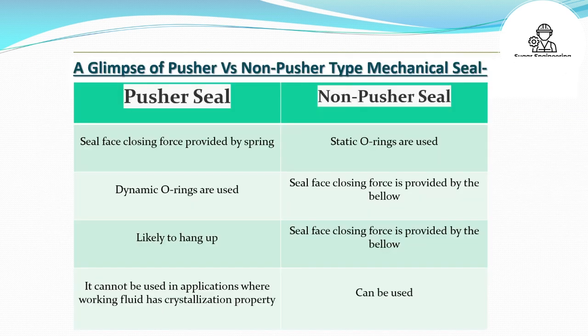A comparison of pusher versus non-pusher type mechanical seal: Pusher seal — seal face closing force is provided by a spring; dynamic O-rings are used; likely to hang up; cannot be used in applications where the working fluid has crystallization property. Non-pusher seal — static O-rings are used; seal face closing force is provided by the bellows; can be used in such applications.